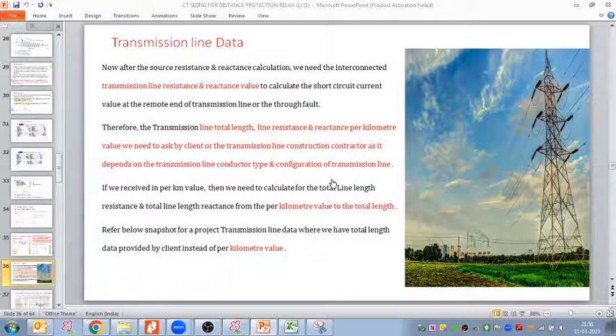Okay, Mustaqil Alam, I think I replied to your query as well. So just give me your next one. Now once my source resistance and reactance is done, the 63 kiloampere fault current is taken from the grid regulations. Yes, right, Bharat. Or whatever your subsystem fault current is, you can take that. In India, for 220 kV we have 40 or 50 kiloampere, so I will take 40 or 50 kiloampere. Whatever my grid fault currents and grid regulations are, that is taken here.